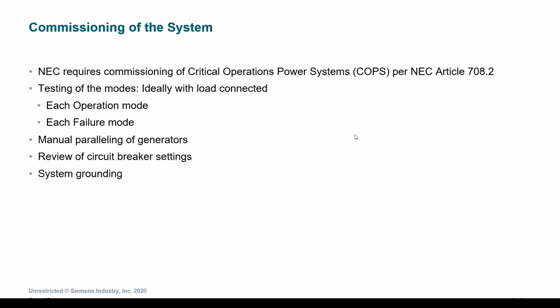Another important part of the commissioning is verifying the grounding of the system meets code and that it does not cause any issues between the generators and the paralleling gear and the building ground. One other important thing to check is the alarm indicators to make sure that everything is alarming the way it's supposed to. If there is a failure or something is not working the way that it's supposed to, these alarms are also being transmitted back to a building automation system where the facilities team is alerted in the case of something not going right.